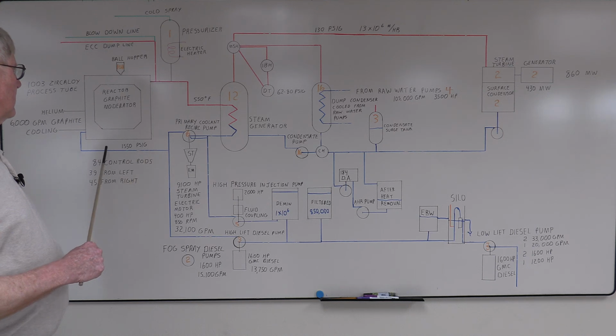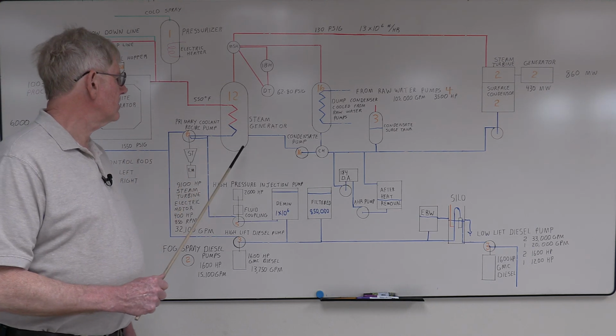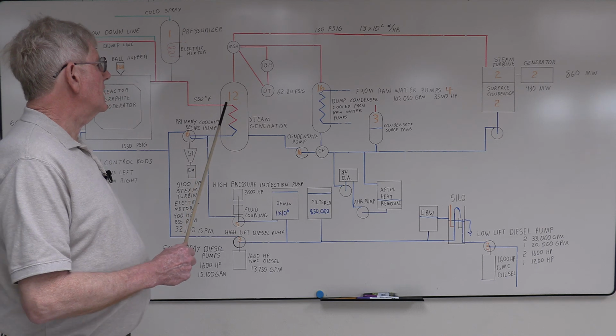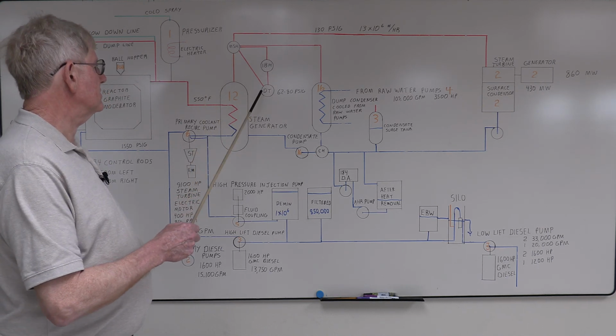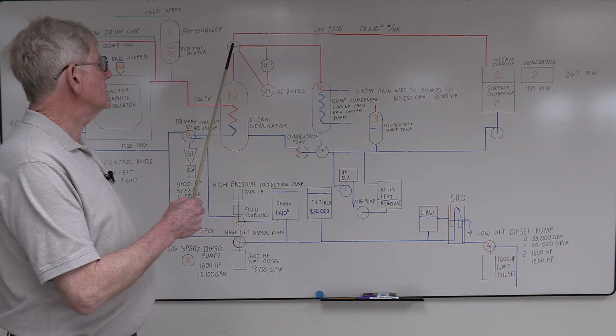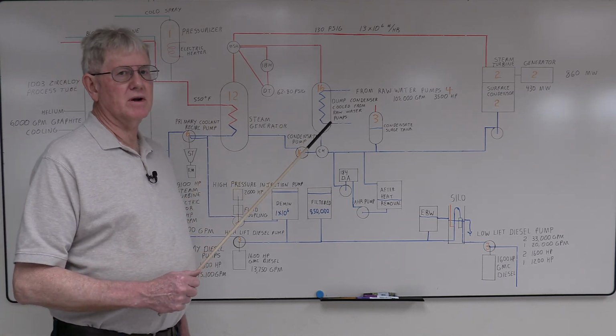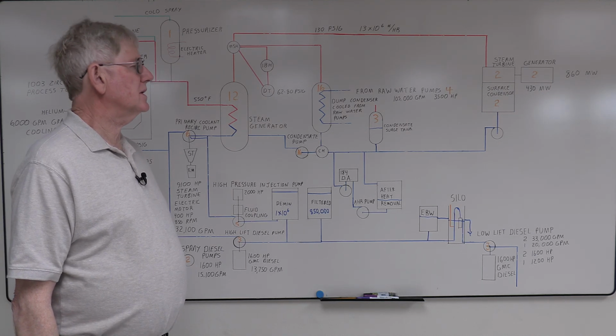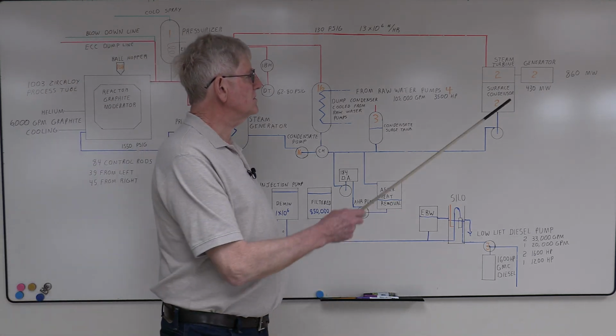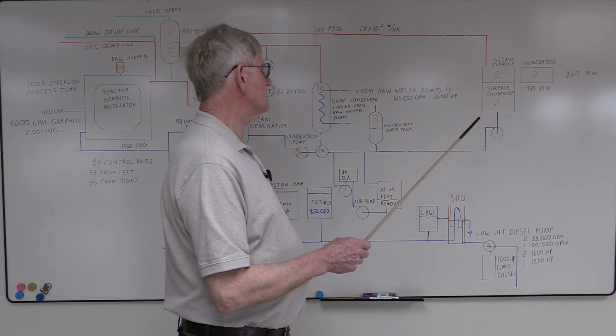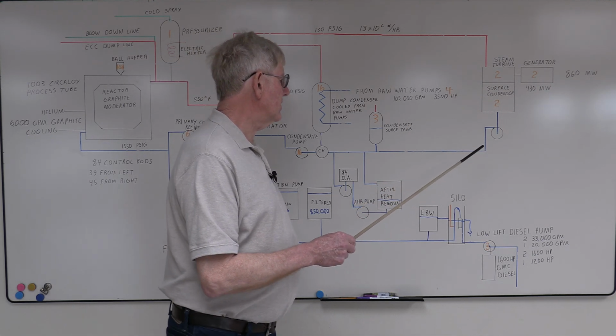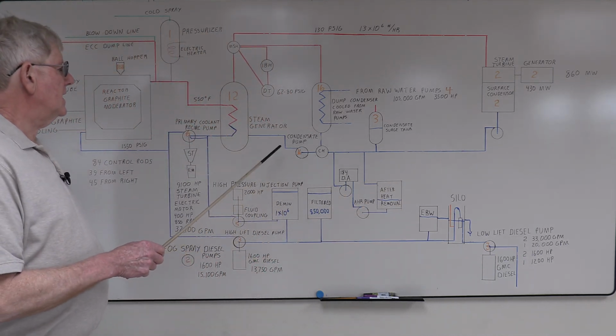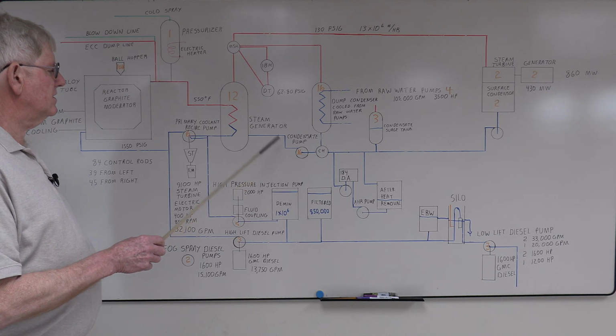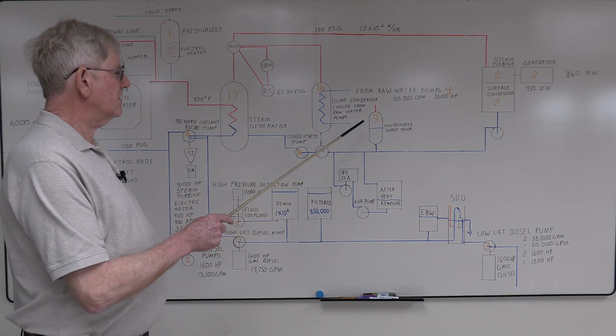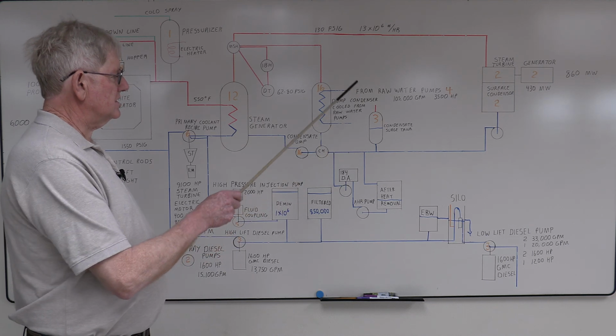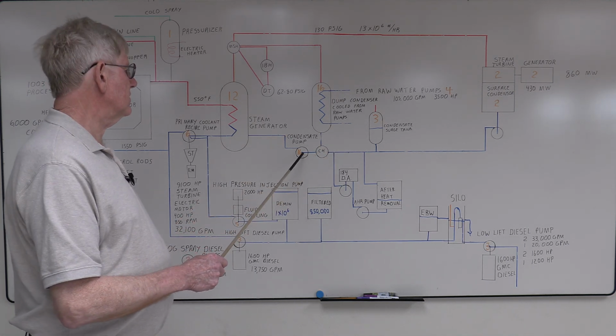So this is one loop of ultra pure demin water. From here, steam was generated, went to the main steam header and was spread through various plant systems. Most of it went over to produce electricity, around about 330 psi, about 13 million pounds of steam an hour. It fed 2 steam turbine generators, put about 860 megawatts, had surface condensers. From there, the condensate was returned back. There were 16 condensate pumps that it fed. There was a surge tank that sat on the system, 3 of them. These had steam blanket on top to maintain net positive suction head for the pumps.